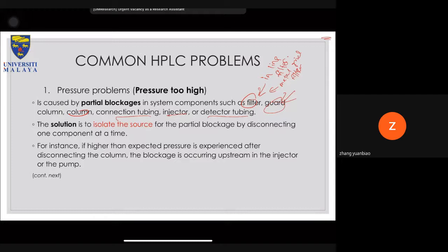So if I were to clean my guard column, I would take the guard column out of the guard column housing, put it in an IPA solvent, and then sonicate it for about 5 to 10 minutes. And then after that, I will rewash it and do it multiple times, I mean the sonication process, while changing the IPA. And for my final wash, I will normally wash it back with either acetonitrile or water, because acetonitrile and water are the main two solvents that I use for my peptide analysis. So simply washing sometimes helps to lower the back pressure.